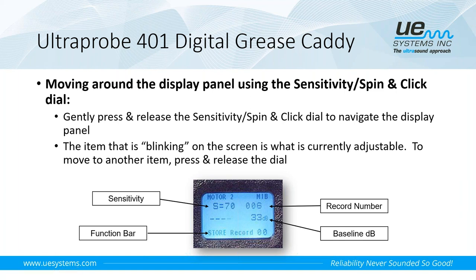Now, the sensitivity has no effect on the decibel level. So if we turn this down too low, to where the decibel level goes away and we get the blinking arrow pointing back to the right, we've turned the sensitivity down too low. We simply turn it back to the right, increase the sensitivity, and the arrow will go away and we'll get our decibel level number. Again, it has no effect on the decibel level. It's just a way for me to bring the instrument into range to be able to measure how much noise that bearing is generating.